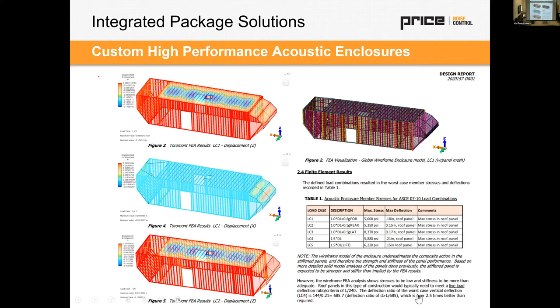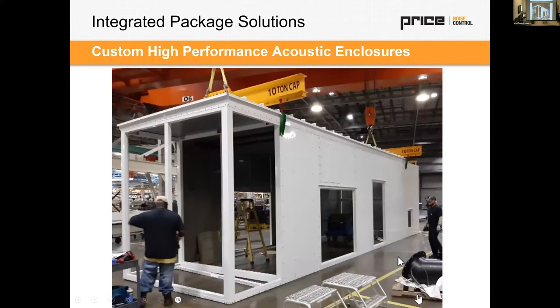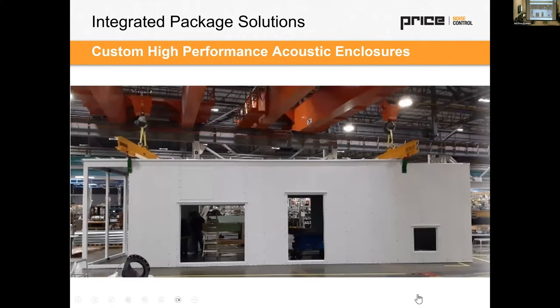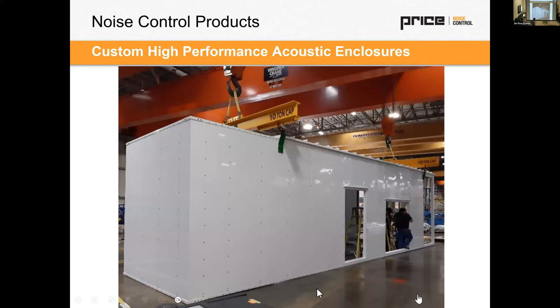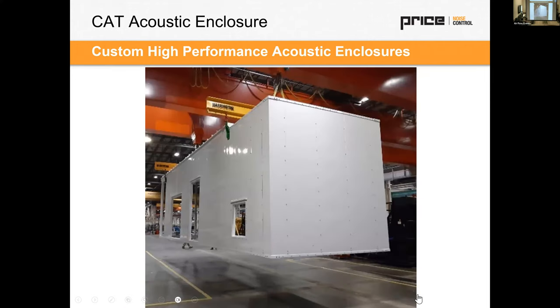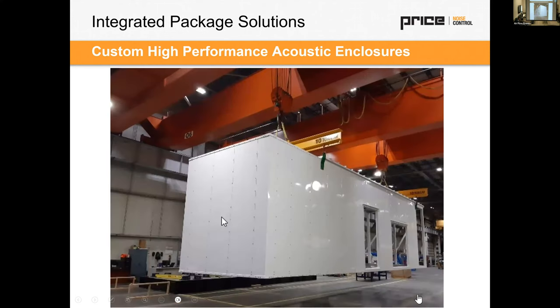This was an interesting generator enclosure, and this is what it looks like. It uses the same tongue and groove interlocking panels as the Jefferson example, but for something the size of a semi-truck trailer, used to attenuate the noise from a generator. One of the complexities of this project was that we designed it to be lifted in a single piece. You can see this is actually off the ground. There's a lot of loading and bracing needed to do that. But the manufacturer of these generators wanted to be able to mount, wire and run the generator in advance of the enclosures coming into play. So it's a really unique solution around generator noise.